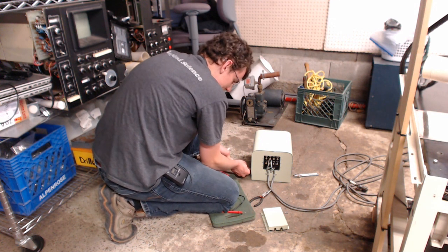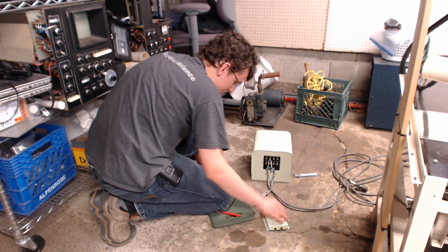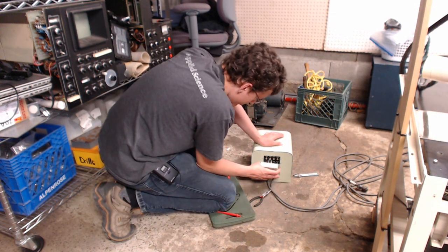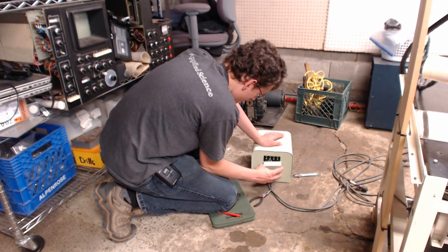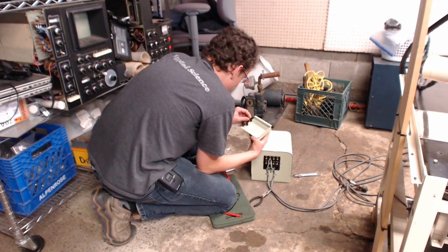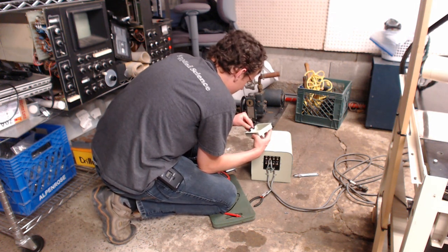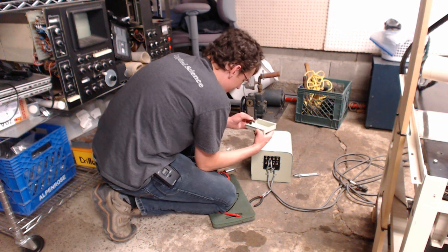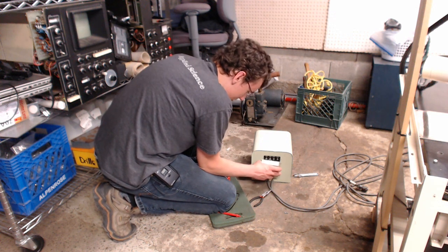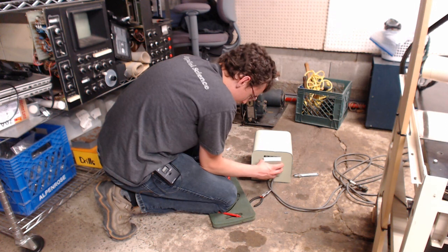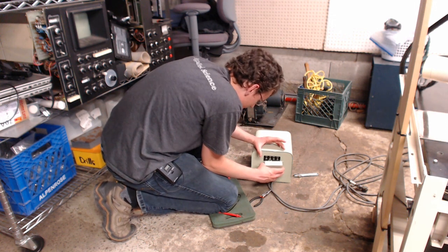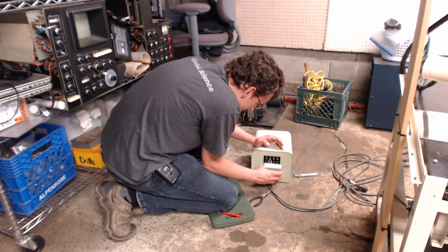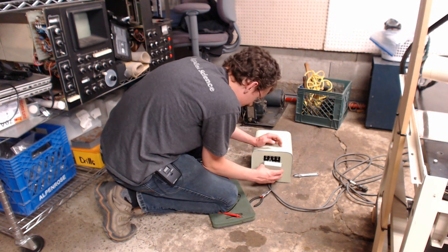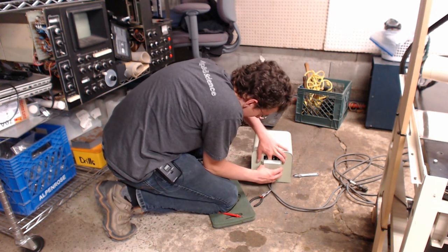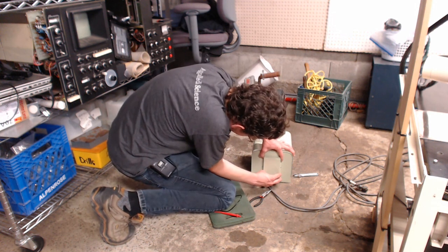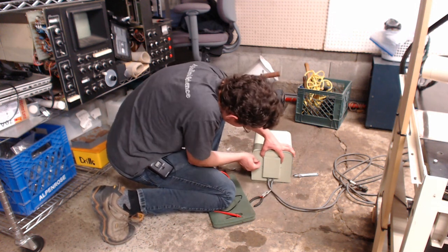If it works out, I'll be able to just convert it from 3-phase to split phase 220. And yeah, there's a motor involved, but you're not doing enough stuff with that motor to really need 3-phase on the motor. And there's also a heater involved. That heater would run just fine with a single phase if it can be wired for it. All right, split phase.